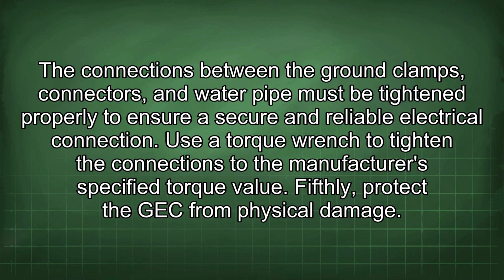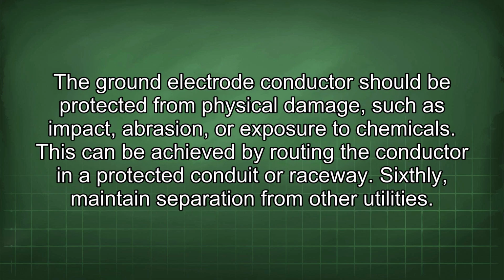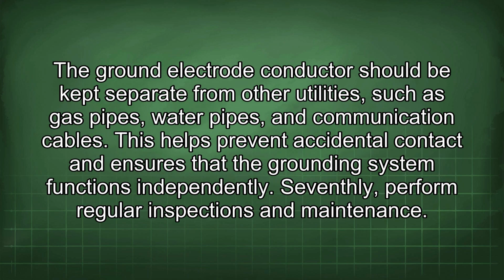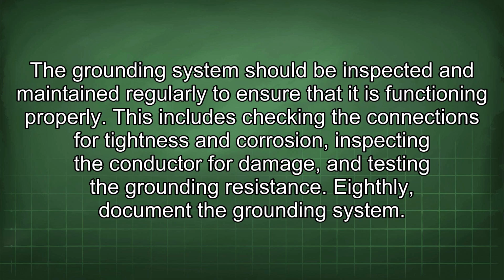Fifthly, protect the GEC from physical damage. The grounding electrode conductor should be protected from physical damage such as impact, abrasion, or exposure to chemicals. This can be achieved by routing the conductor in a protected conduit or raceway. Sixthly, maintain separation from other utilities. The grounding electrode conductor should be kept separate from other utilities, such as gas pipes, water pipes, and communication cables. This helps prevent accidental contact and ensures that the grounding system functions independently. Seventhly, perform regular inspections and maintenance. The grounding system should be inspected and maintained regularly to ensure that it is functioning properly.